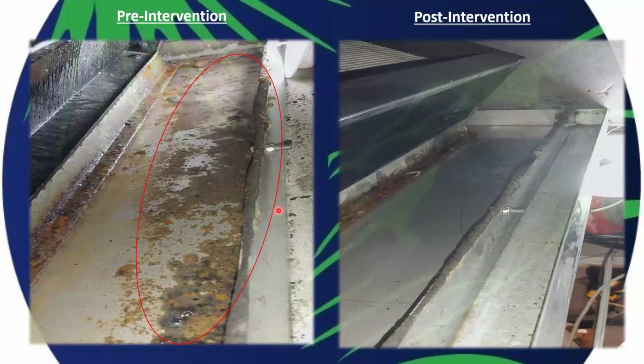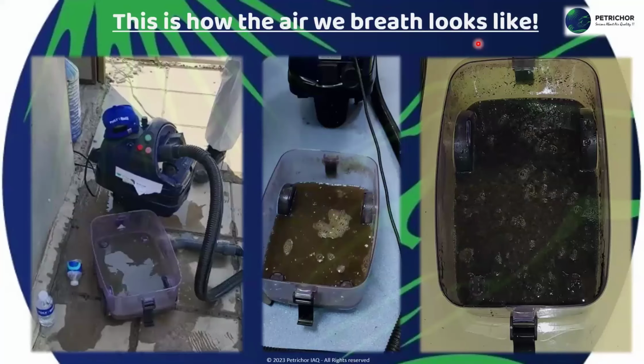Again, more drain pans, more issues. We took a look at the filters, we found the same thing. The blower motors, I would say 100% of the time, I've never seen somebody sanitizing a blower motor because they don't have the means to do it. You can't drop chemicals on a blower motor. But everything inside that fan coil cabinet, we need to keep in mind, is being contaminated.